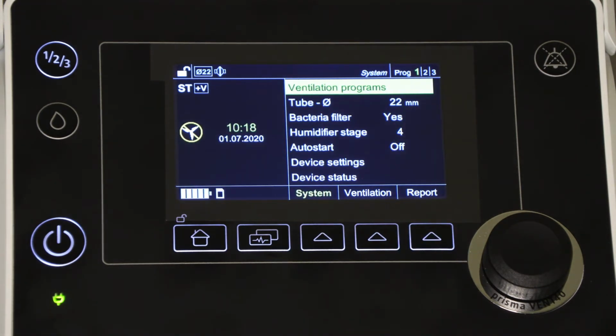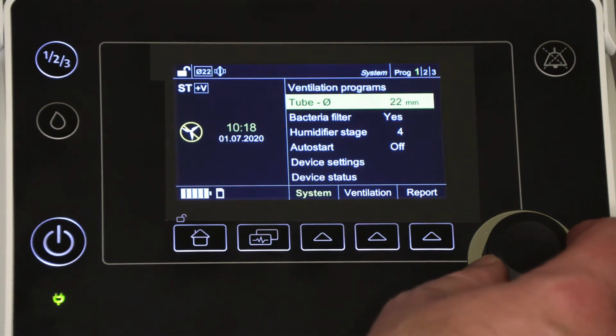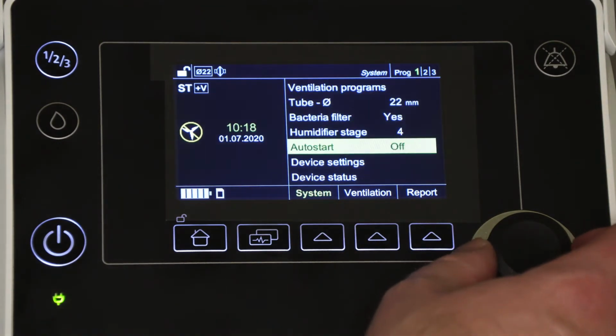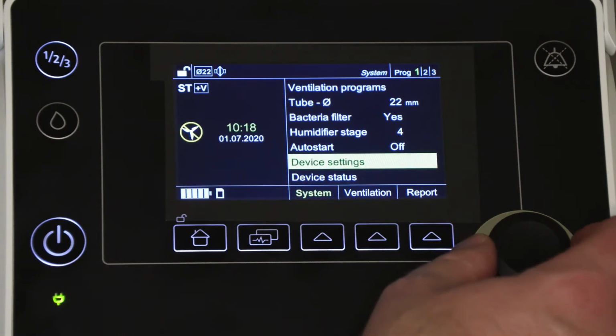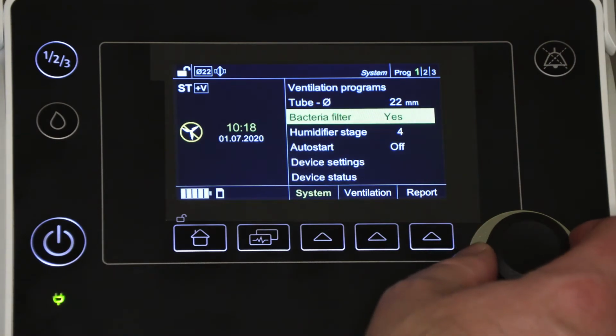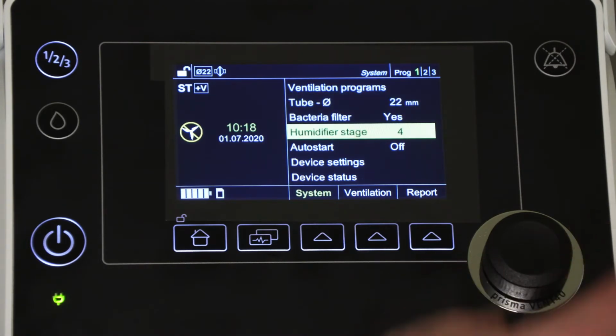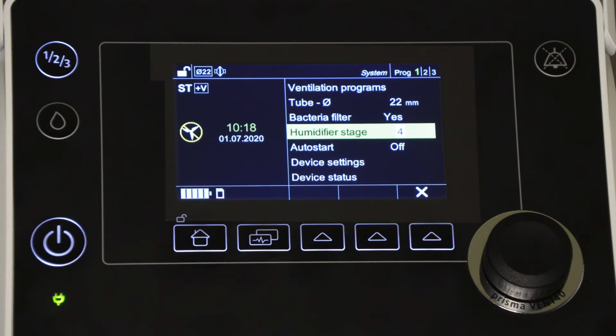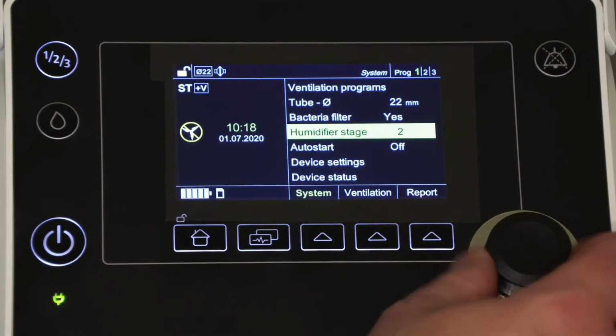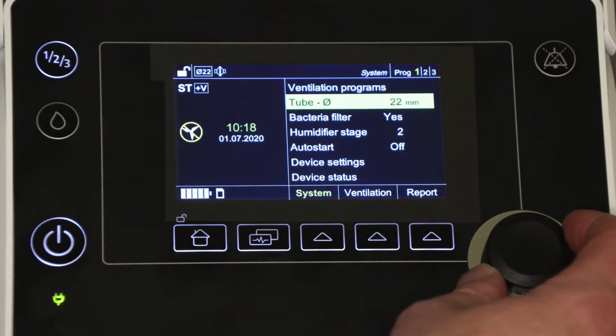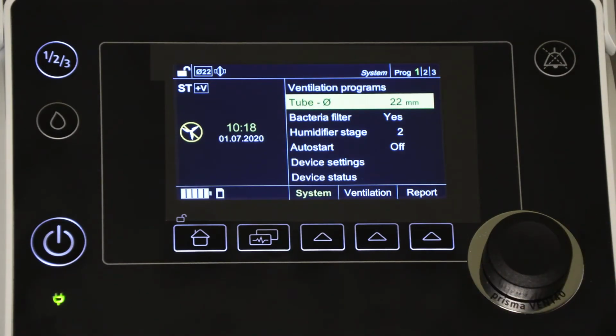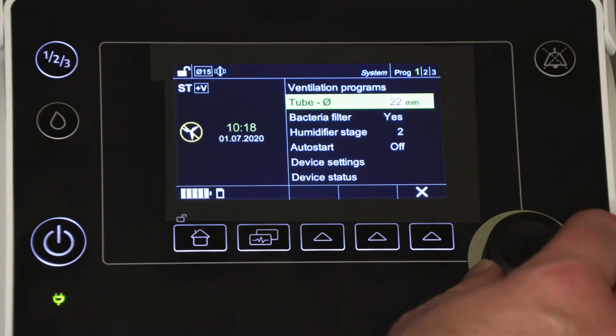Once you're back to this menu, you can turn the rotary knob to select another part of the menu to adjust. This is how easy it is to use the rotary knob to navigate any menu. Simply turn the wheel until you reach a part of the menu that you want to adjust, press it to enter the setting, turn to adjust, and press again to confirm. The next item in the System menu is the breathing tube diameter. This is set to 22mm by default, but if you want to use a 15mm breathing tube with the ventilator, then you'll need to change this setting.